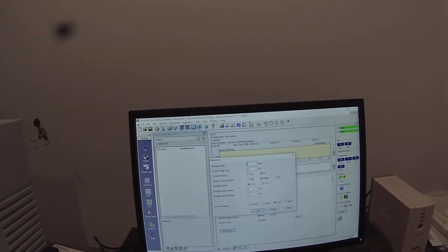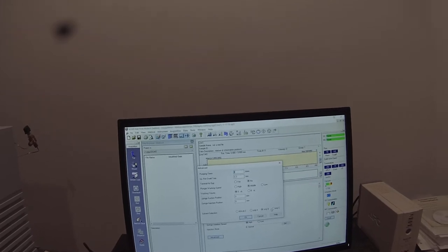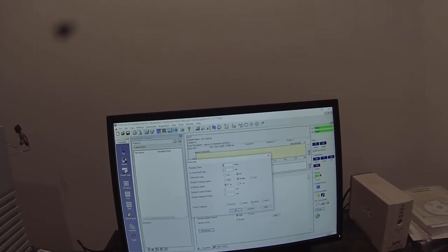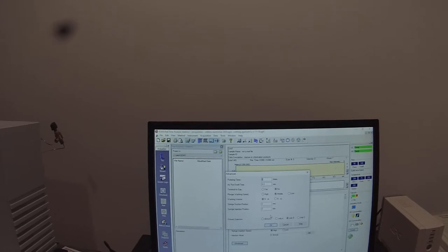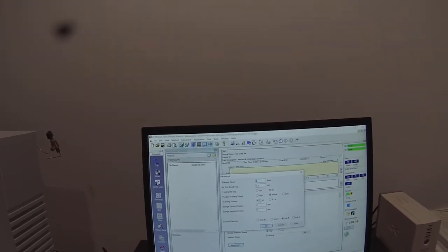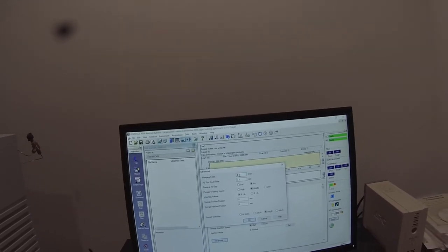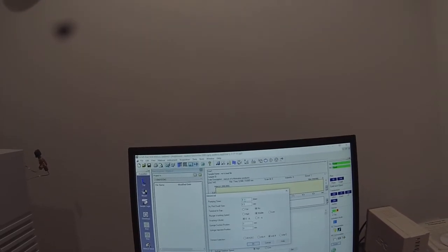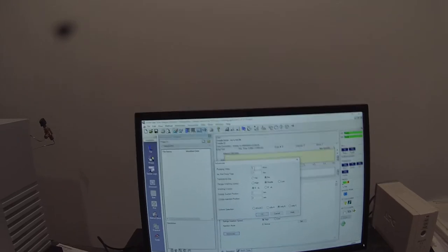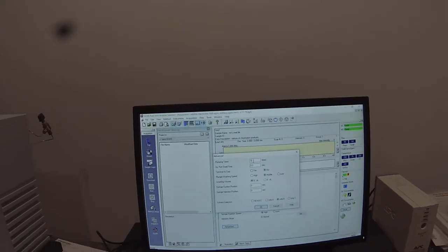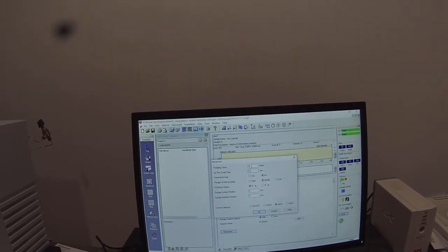And if we go to the advanced mode here, it'll tell us that the solvent we're washing with is just B, right? Just the dichloromethane and not the methanol and the hexane. And it's going to wash with 6 microliters at a time. And this pumping time, that's to get rid of air bubbles. It's going to pull up the solvent, 6 microliters of it, and then quickly eject it. Pull it up and eject it, pull it up and eject it. That'll get rid of air bubbles.